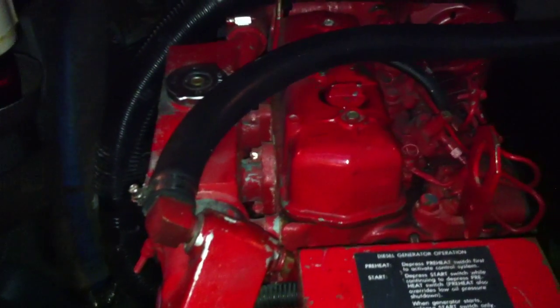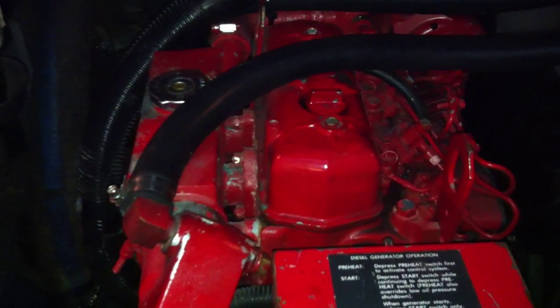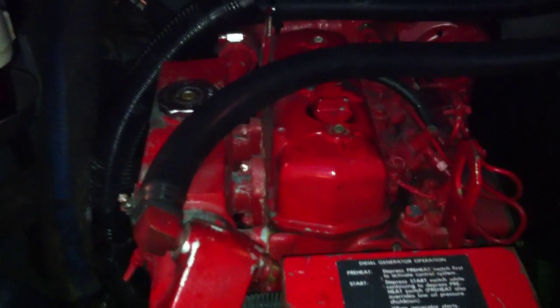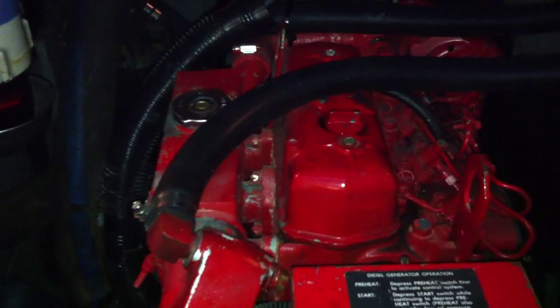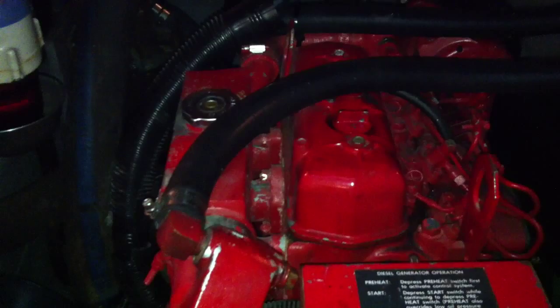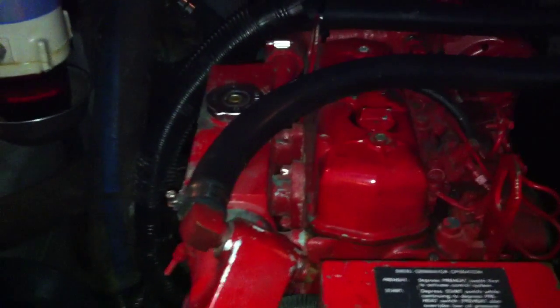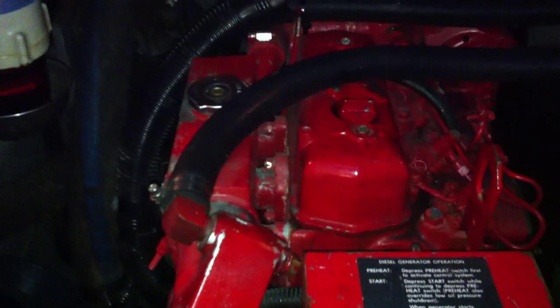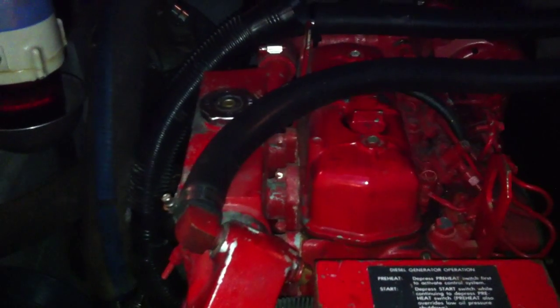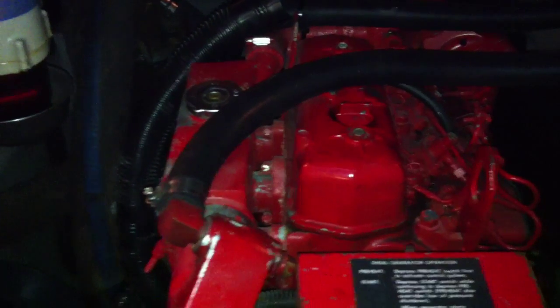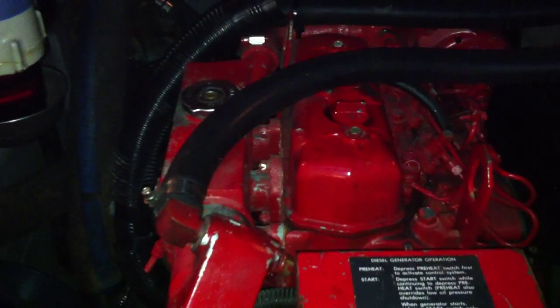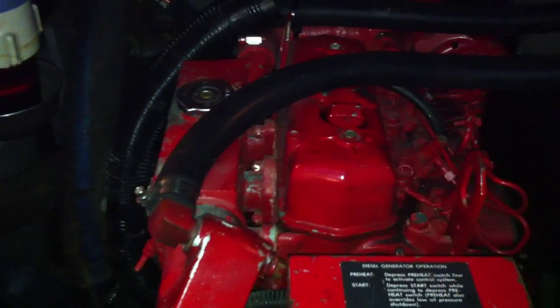Usually, especially if you're doing a lot of shallow running, you've got silt and things like that going in there, possibly grinding that rubber up and burning the impeller out. Some people say once every two years they change their impellers. We end up being in a lot more shallow water in different anchorages and places like that, so we typically try to change those every year or so, plus we put a lot of hours on our generator. I don't know if you can see here or not, but I think it's 1,411 hours on this generator.